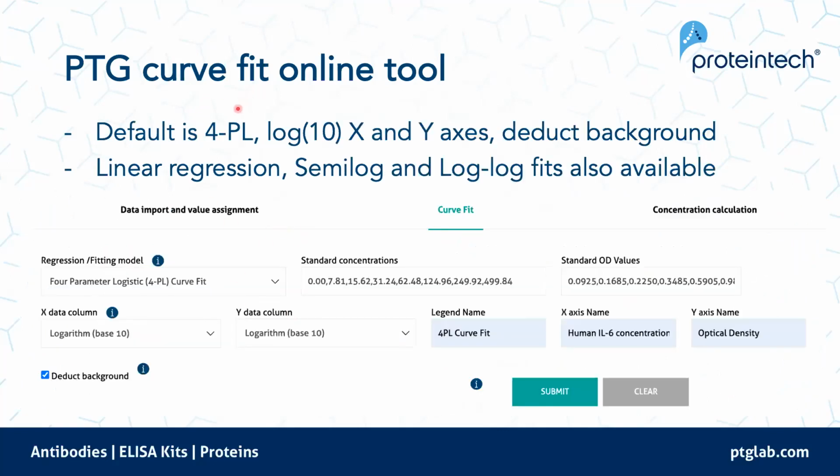Also, along with our curve fitting tool, because we know that the 4-parameter logistic, the 4PL, is the best curve fit, the default setting is 4PL, and then also logging the X data and the Y data, so the OD and the concentration. And we've also set it to automatically deduct the background. These can all be played with. You can change your regression fitting model to something like a linear regression or a semi-log fit, and you can also have the flexibility of naming it yourself.